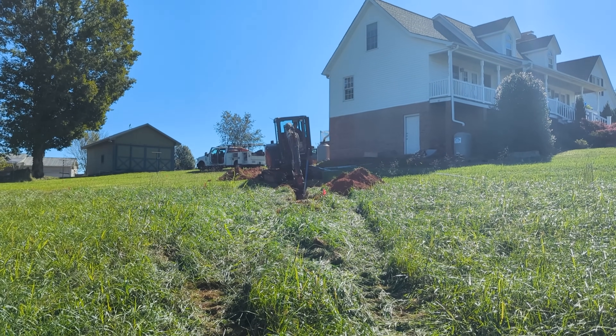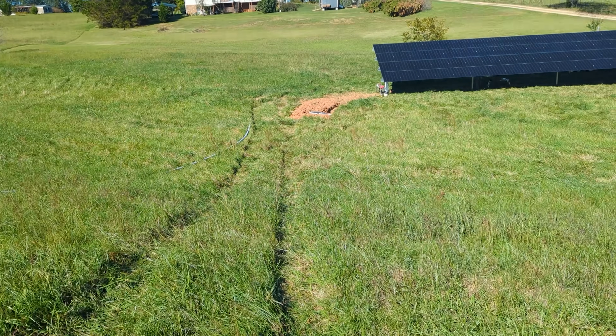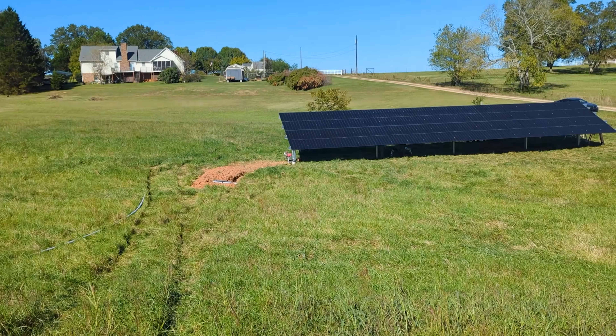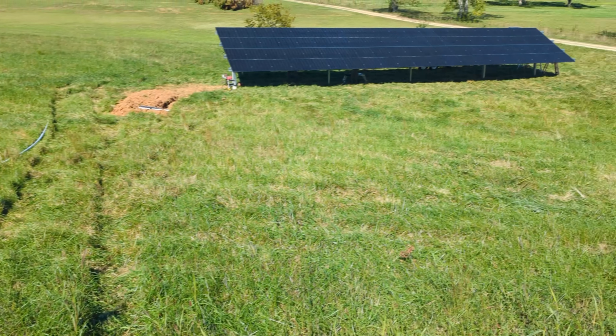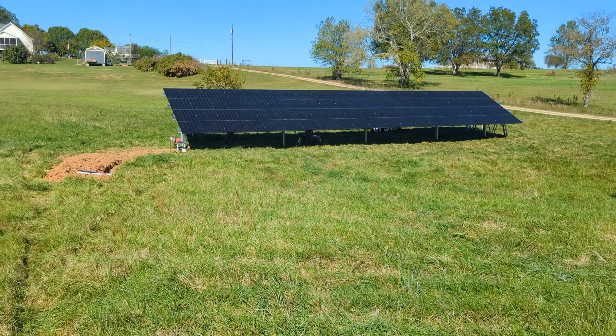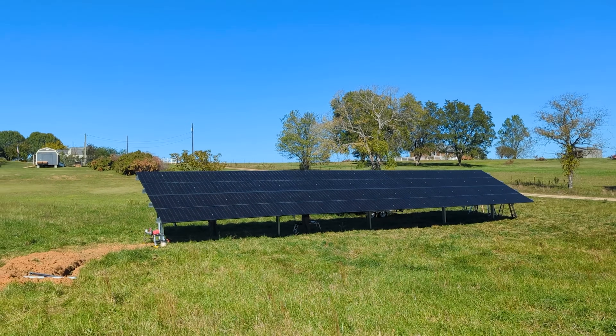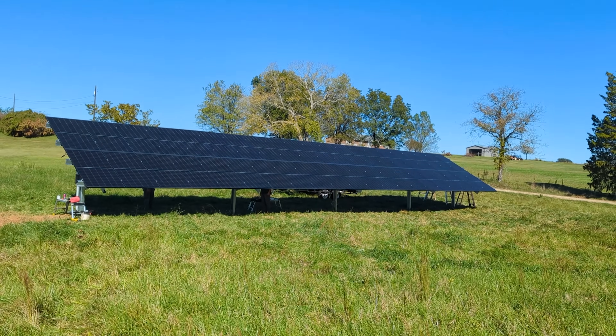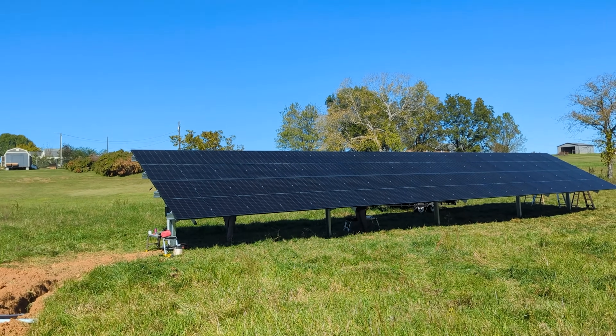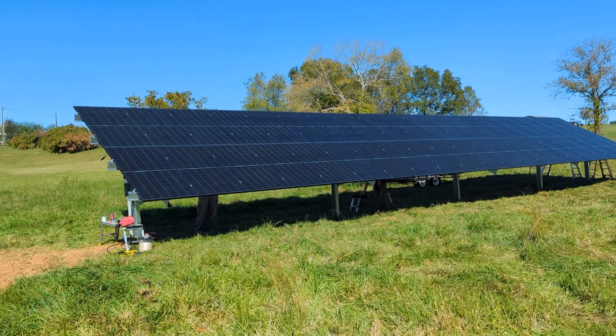I was digging up at the house and I've gotta go somewhere else, so I'm gonna leave these guys to dig and get the pipe in — we'll be back tomorrow. Single 15k and a stack of Giga Stacks — we've really enjoyed these batteries, enjoy working with James Mast up in Millersburg, Ohio. These 42-panel arrays wire nicely with a 15k, very balanced. With 450-watt panels, 28s and 42s make really nice stringing. The inverter is the hub that drives the stringing — in my opinion, the design should be built all around the inverter.